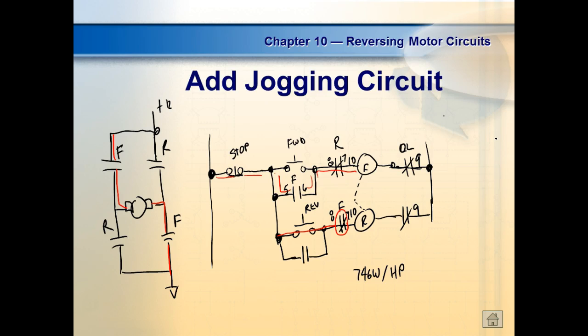It happens every class. Because you see 8 and 9, and you're up here working in the forward circuit, and you hook it up to 8 and 7. You're working on the forward circuit, you see 8 and 7, you want to hook it up to 8 and 7 on the forward circuit. But that is not the forward circuit, that's the what? Reverse. So you got to run it from 8 and 7 over to your other relay.